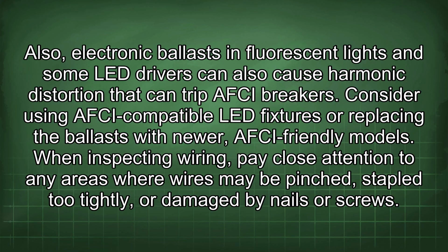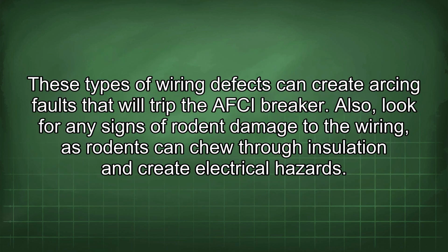When inspecting wiring, pay close attention to any areas where wires may be pinched, stapled too tightly, or damaged by nails or screws. These types of wiring defects can create arcing faults that will trip the AFCI breaker.